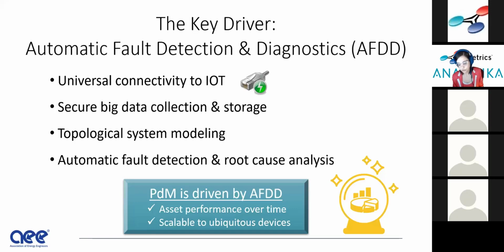In order to find root causes, right, accurately, and to get at the real problem, we need to see the interconnectivity of all of the equipment. A fault downstream might be caused by something upstream. There could be the fault of a ubiquitous small piece of zone equipment that can be causing a problem. So we need to look at everything. And I'll talk about that scalability that I kind of mentioned.